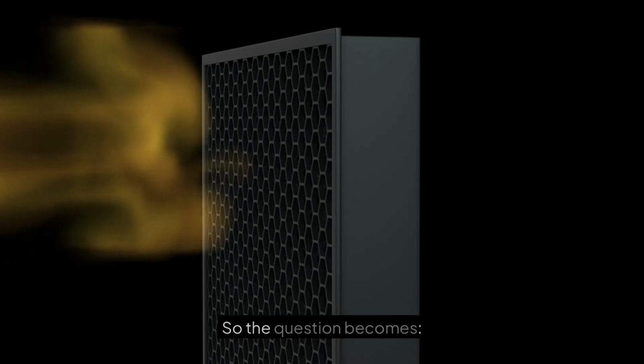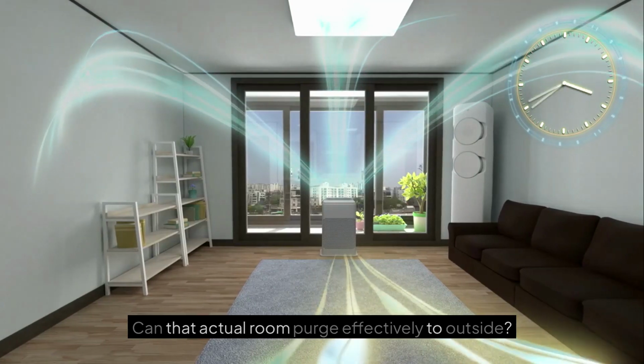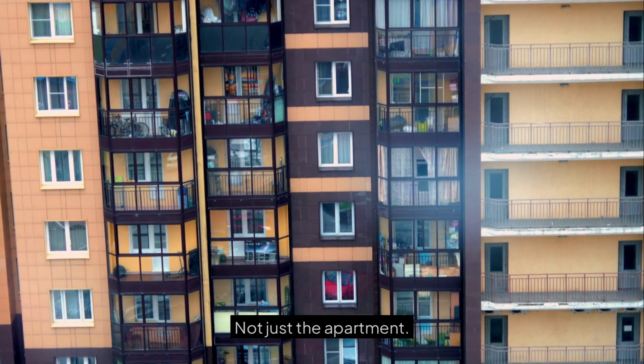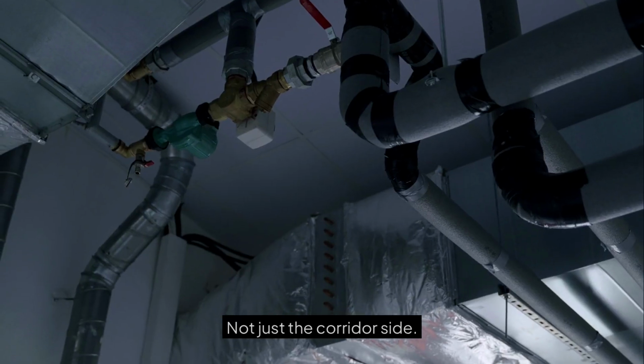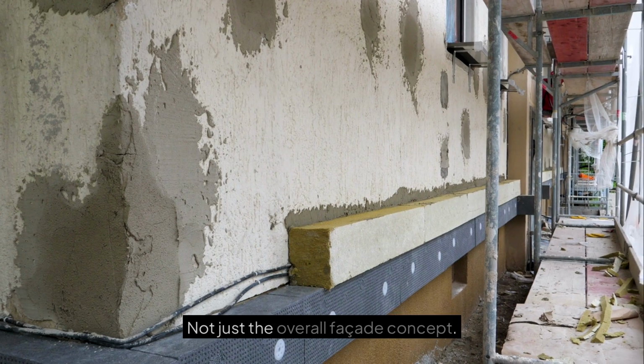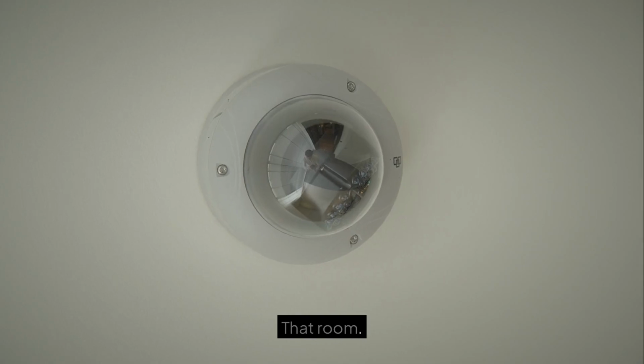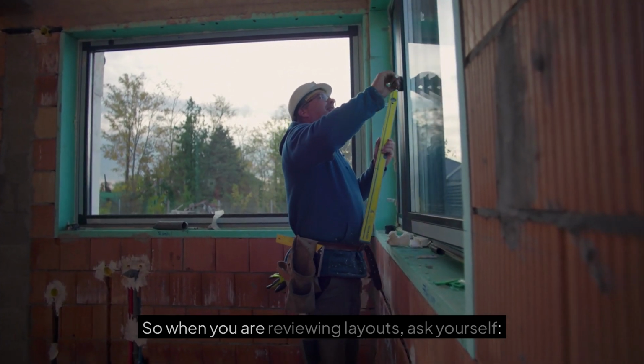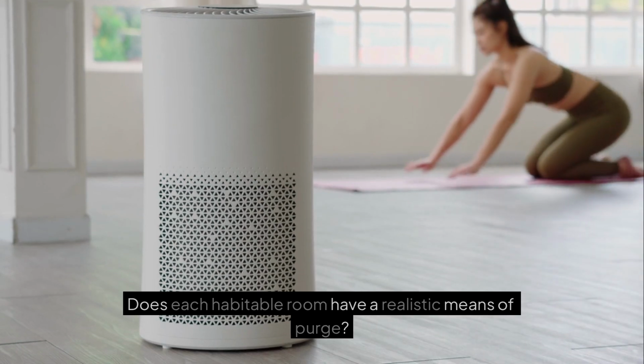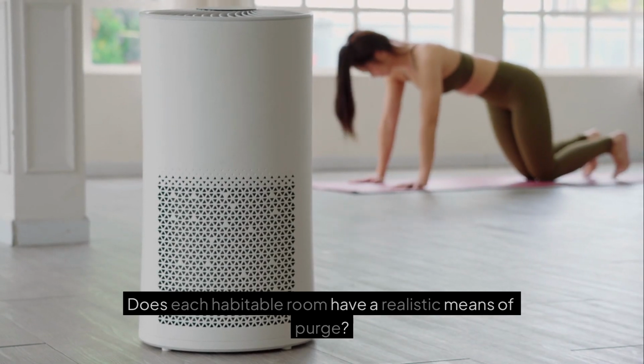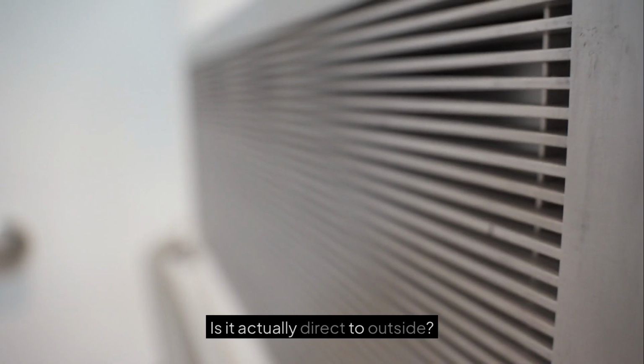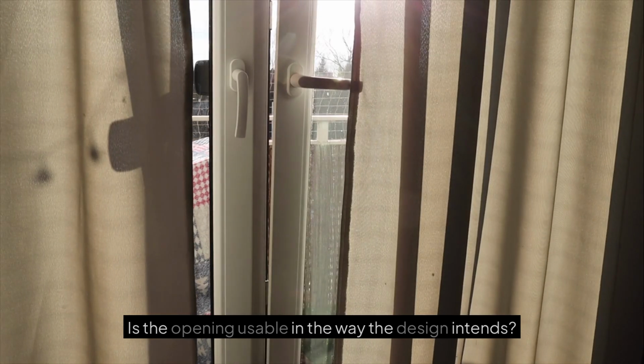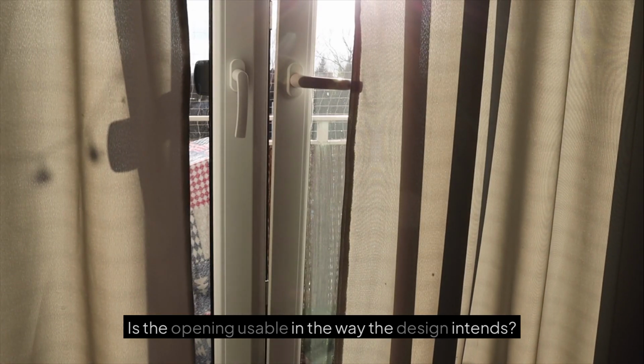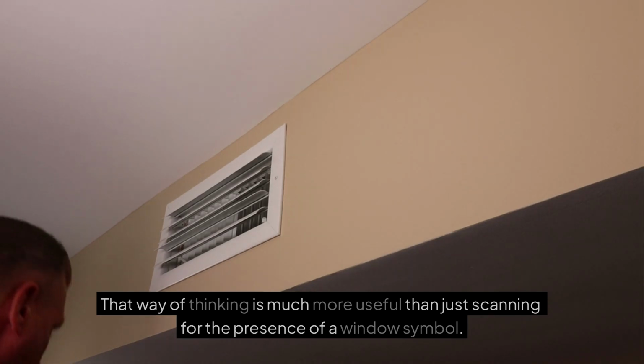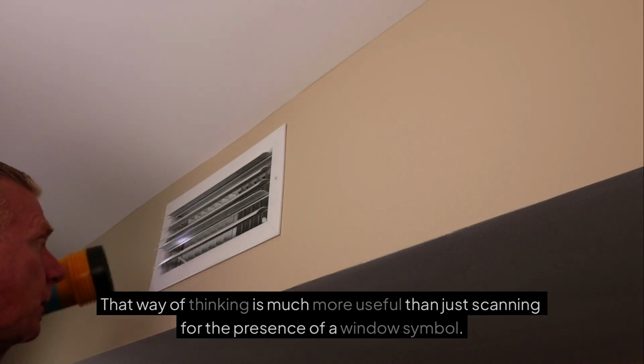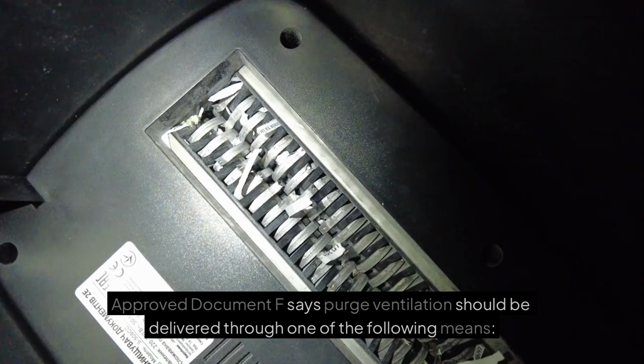So the question becomes, can that actual room purge effectively to outside? Not just the apartment, not just the corridor side, not just the overall facade concept. That room. So when you are reviewing layouts, ask yourself, does each habitable room have a realistic means of purge? Is it actually direct to outside? Is the opening usable in the way the design intends? That way of thinking is much more useful than just scanning for the presence of a window symbol.